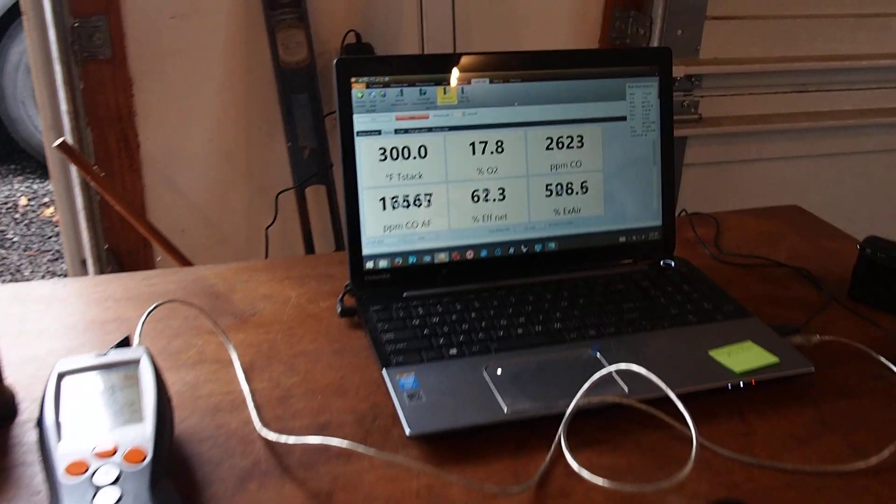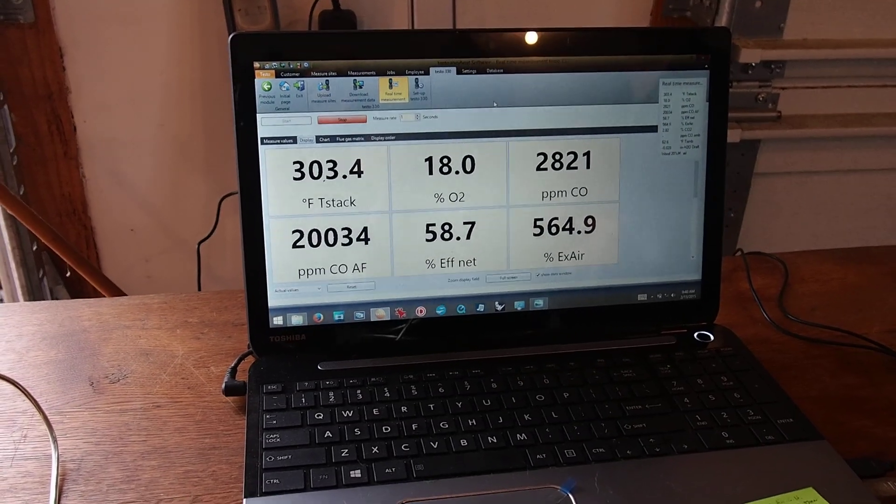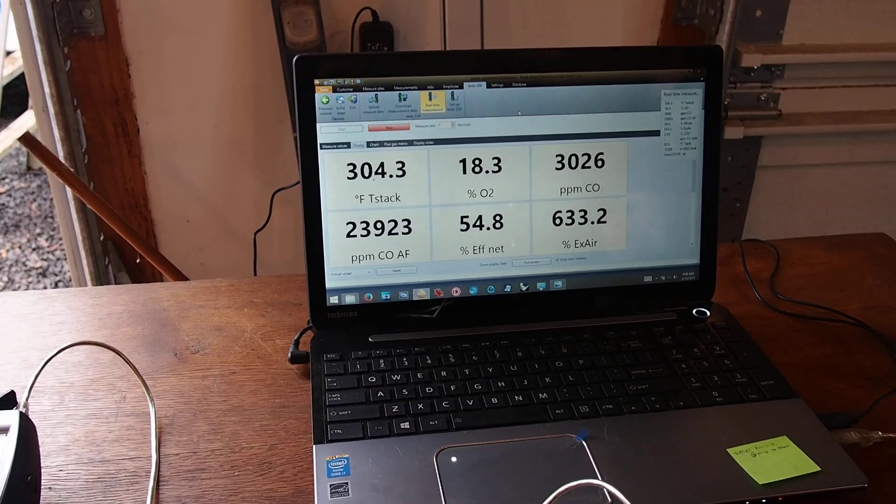You can see here the stack temperature is around 300 degrees. We just put the fuel in so it's likely we're going to get a CO spike.